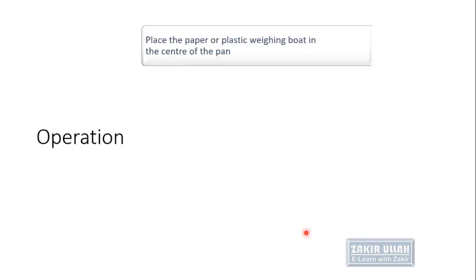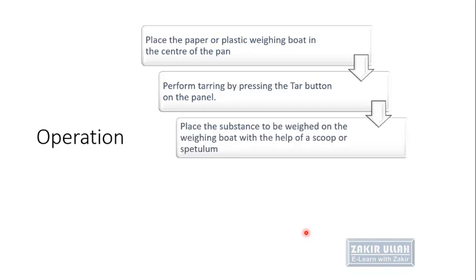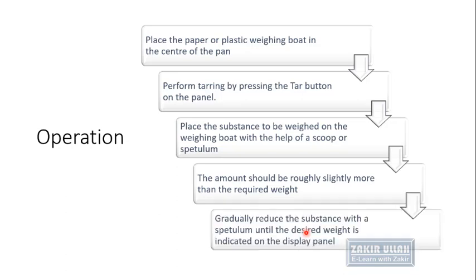To operate an electrical or electronic balance: first place a paper or plastic weighing boat in the center of the pan, then press the tare button on the panel to zero the balance, which calibrates it. Then place the substance to be weighed on the weighing boat using a scoop, spoon, or spatula — the amount should be slightly more than the required weight. Then gradually reduce the extra mass using the spatula or spoon until the required mass is shown on the display panel.